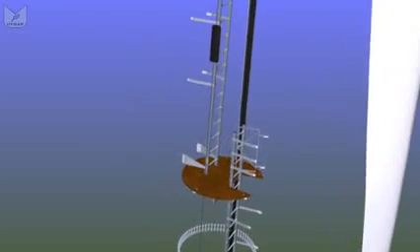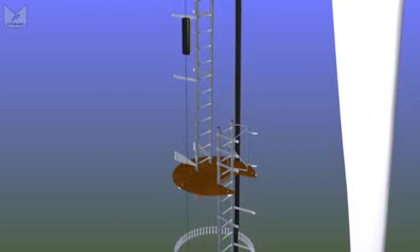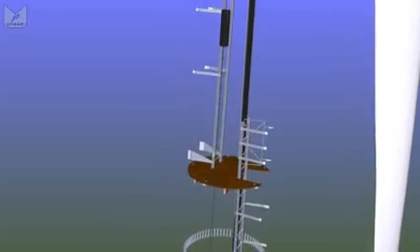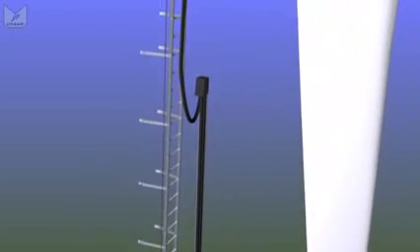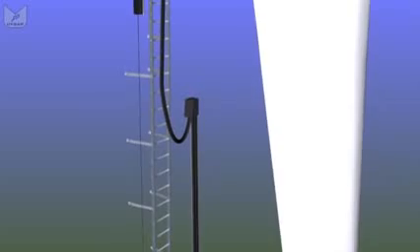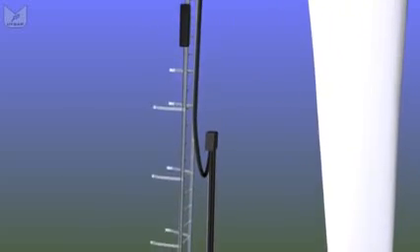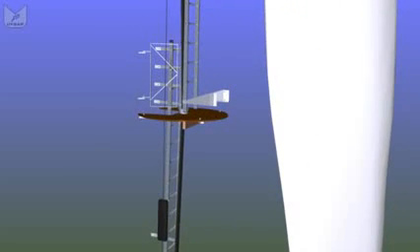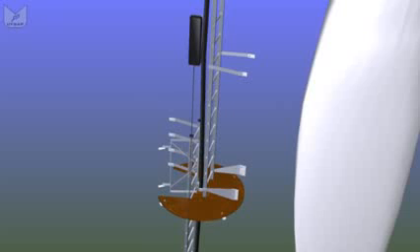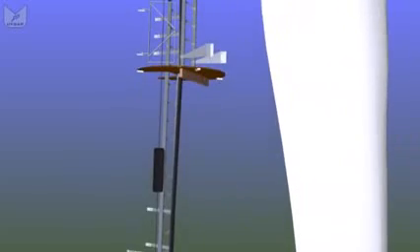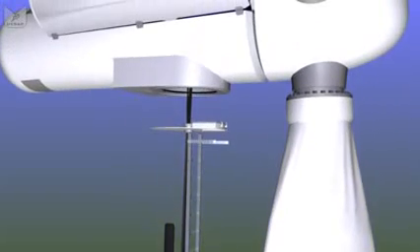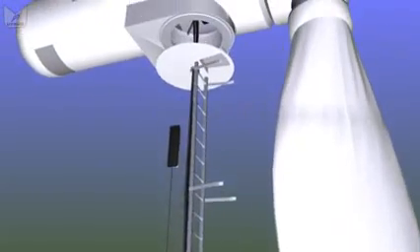But eventually the main cables stop being attached to the wall and they hang freely in the center of the tower, so they can twist as the nacelle rotates to face the wind. If they twist too many times, the nacelle will spin itself around to remove the twists. As we move up, now the cable goes through a hole in the center of each platform, and at the top of the tower we have a steel platform with a sealed trapdoor, which we call the yaw platform.